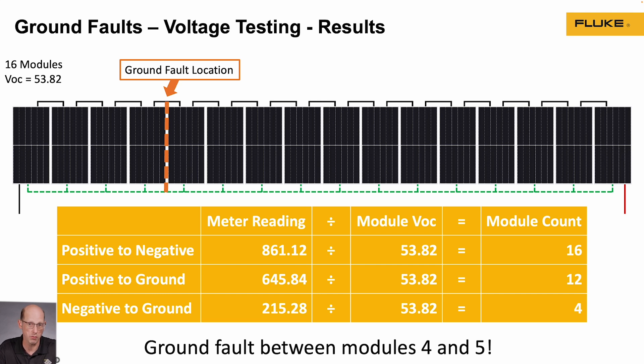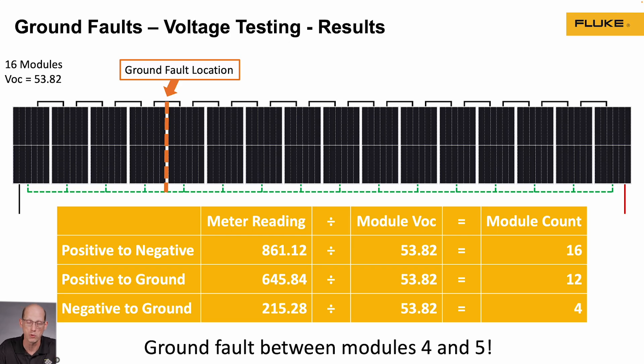With this information, I can go out into the field, get my diagram out, figure out where this string is located, identify the negative end of the string, count in four modules, and then do a visual inspection to see if I can identify the cause of the ground fault.